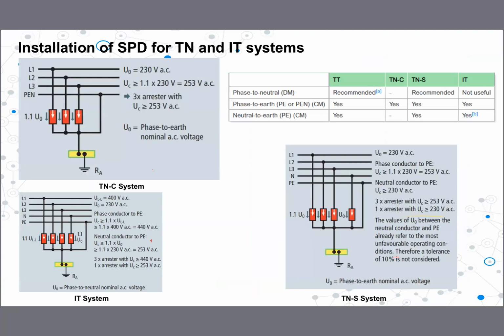Then, just for your information, how to install SPDs in other systems, right? Other earthing systems. Actually, we don't commonly have other systems here, rather it's a special type of installation, right? So this is how we install SPDs in the TNC system, right? Only 3 SPDs between the phases, right? There is no SPD in the PEN conductor, right? Then in the TNS system, we need 4, between the 3 phases plus the neutral, and we common them with the protective earthing and connect it to the earth terminal, right?